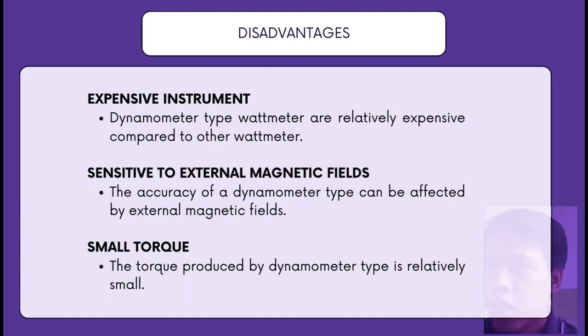Next, the disadvantages. First, expensive instruments. Dynamometer type wattmeters are relatively expensive compared to other wattmeters. Next, sensitive to external magnetic fields. The accuracy of a dynamometer type can be affected by external magnetic fields. Lastly, small torque. The torque produced by a dynamometer type is relatively small.